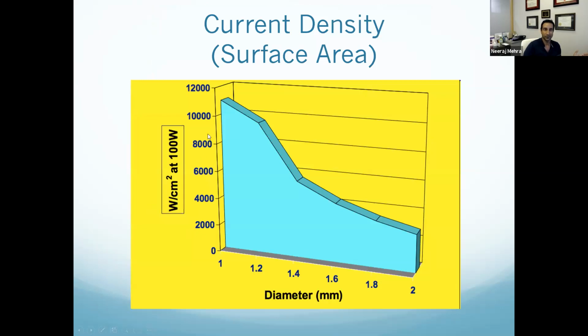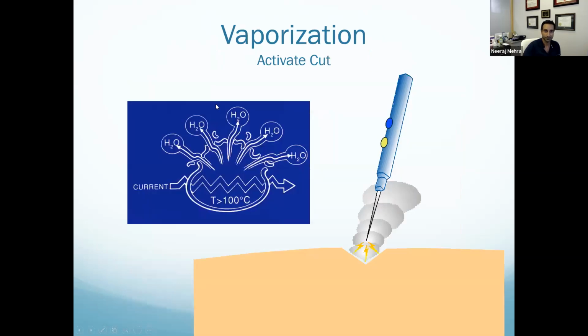Where it really plays out is you can see that even a small change in diameter gives massive changes in the amount of energy that's going through your current density, because it has to do with surface area. So you cut the diameter in half, and you've massively increased your current density. So that's what's happening when you vaporize something.